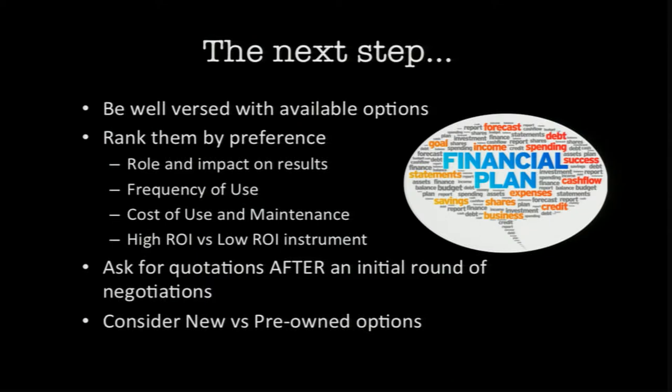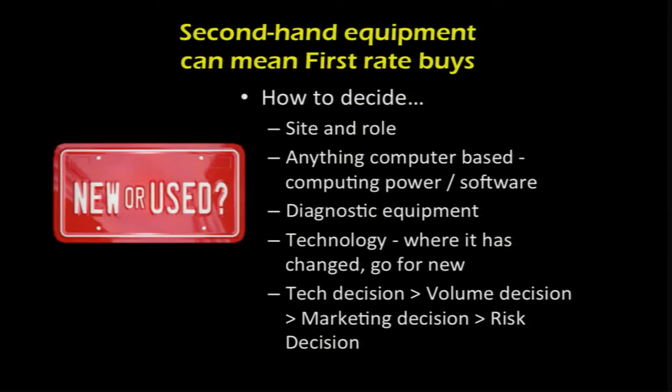A very good option is to consider second-hand equipment. Now, second-hand equipment does not always equate to bad equipment. How do you decide whether you're going to go for new equipment or second-hand equipment? If your role of equipment is to be the primary equipment, or it is a diagnostic equipment on the basis of which you're going to take treatment decisions, you probably are better off going for newer equipment. Anything that is computer-based, has a lot of computing power required, or a software upgrades, it is always better to go for new equipment.